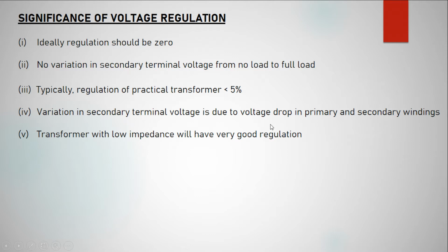Variation in the secondary terminal voltage is due to voltage drop in the primary and secondary windings. Why does voltage regulation arise? Because of the secondary terminal voltage variation. Why does that variation occur? Because of the voltage drop in the primary and secondary windings. When current starts flowing in the windings, there is a significant voltage drop, and because of this, voltage regulation increases. The transformer with low impedance will have very good regulation. That is one hint given. So that's about voltage regulation.